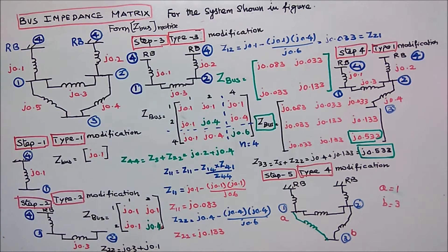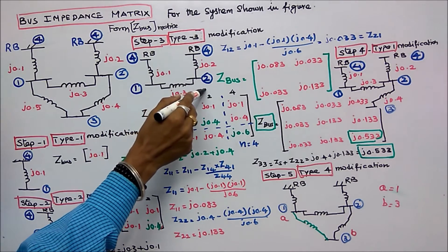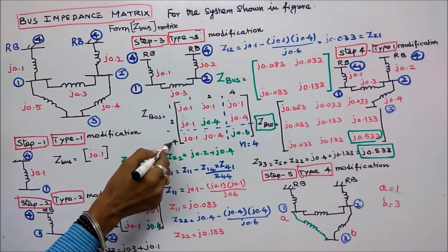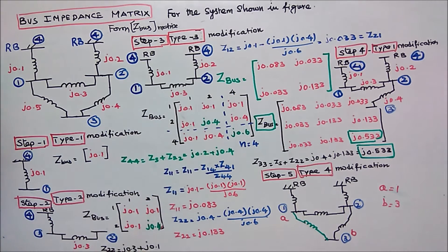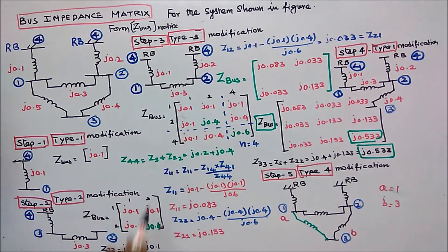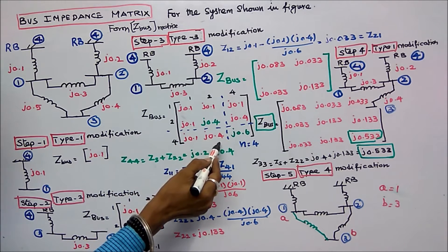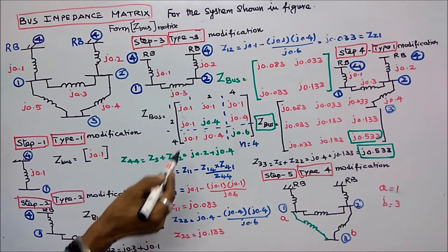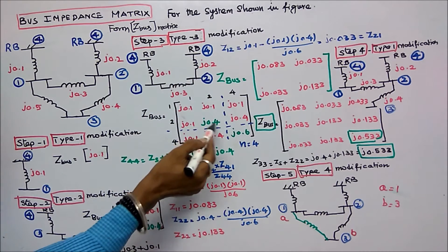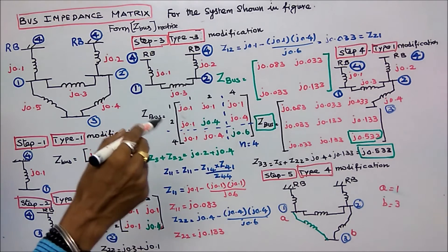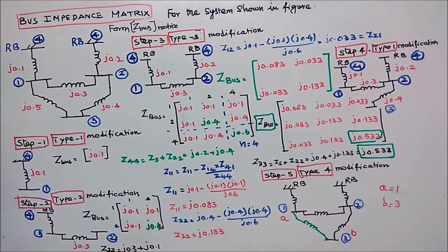Step three is a type three modification. I am connecting bus two to the reference bus four. Now I got a three by three matrix. The old matrix values are: Z11=j0.1, Z12=j0.1, Z21=j0.1, Z22=j0.4. Z44 equals Zs plus Z22; Zs equals j0.2, Z22 equals j0.4, so Z44 equals j0.6. Now I have to eliminate the reference bus using Kron's method.